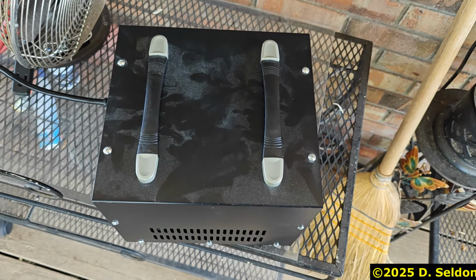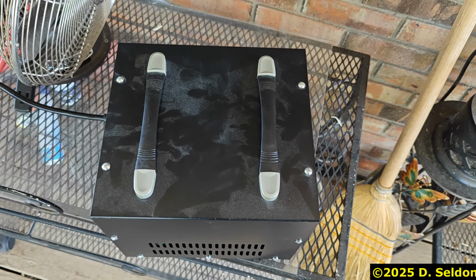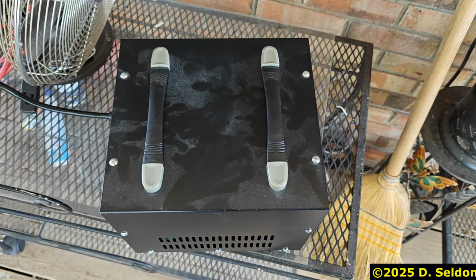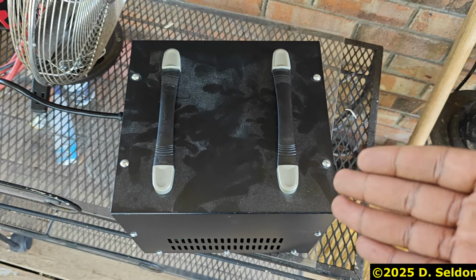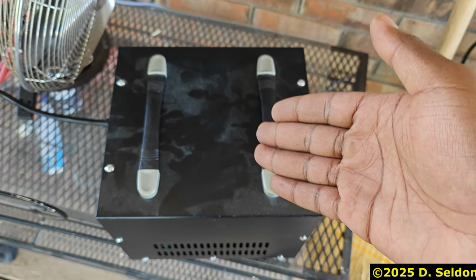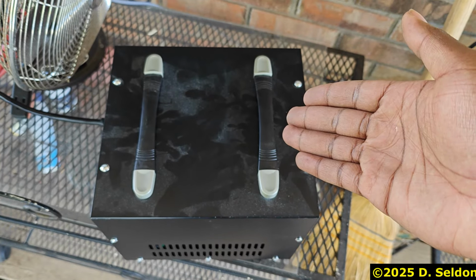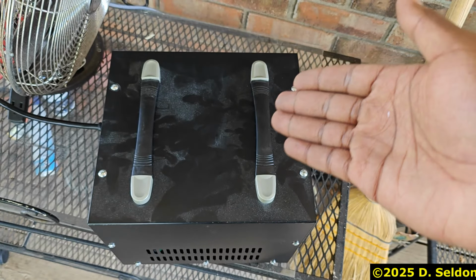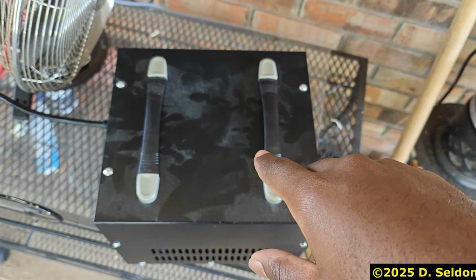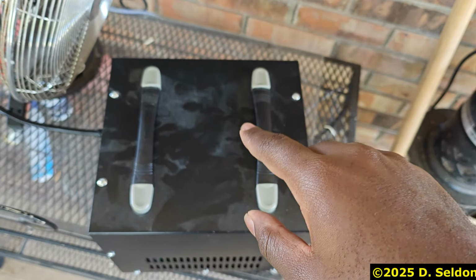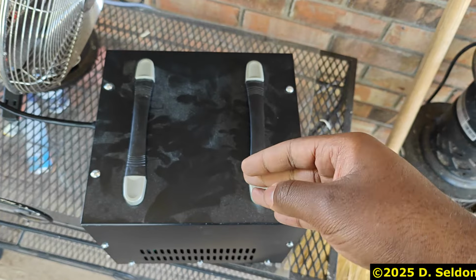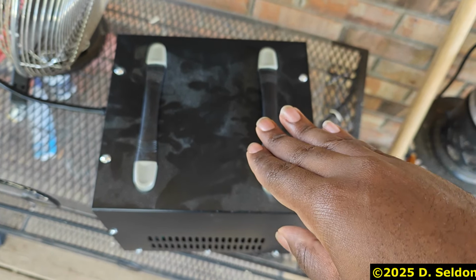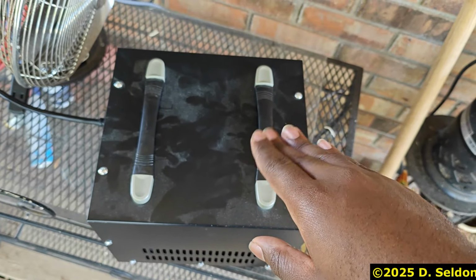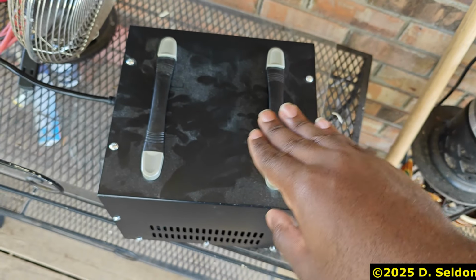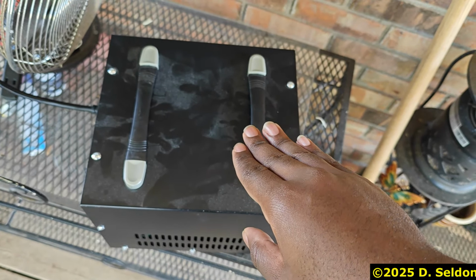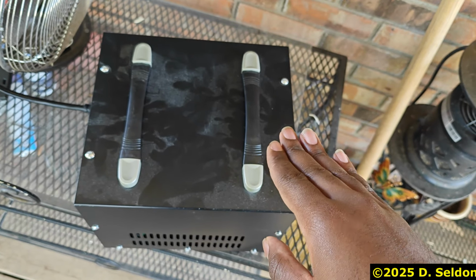That circuit was meant for a 15 amp breaker. They switched it over, and it's sufficient for the Model 1 because it's a 1 horsepower siren that runs on 110 and pulls 8 amps. The Model 2 is a 2 horsepower siren that runs on 120 volts, basically the same as 110, but it draws 24 amps. I think the reason those numbers aren't symmetrical, why it draws 3 times the power, is that the Model 2 isn't quite as efficient as far as the motor is concerned.